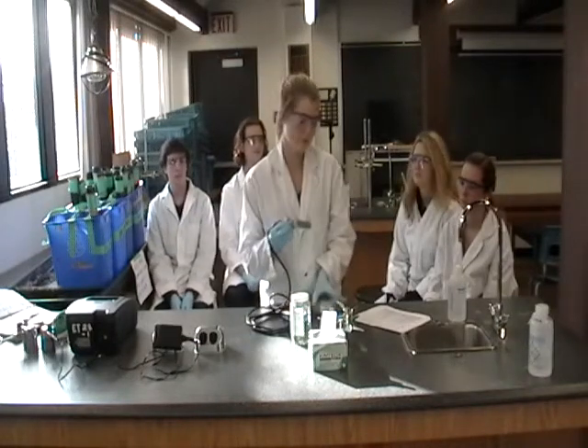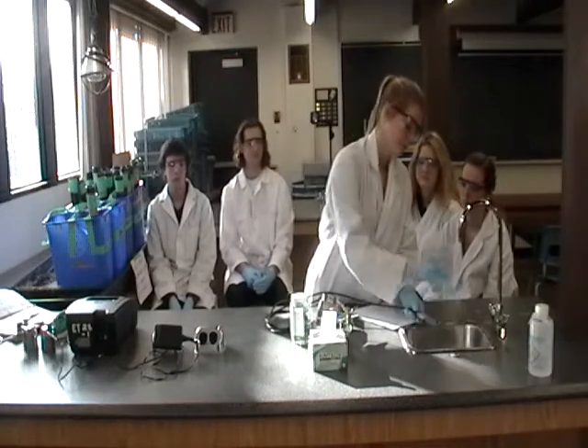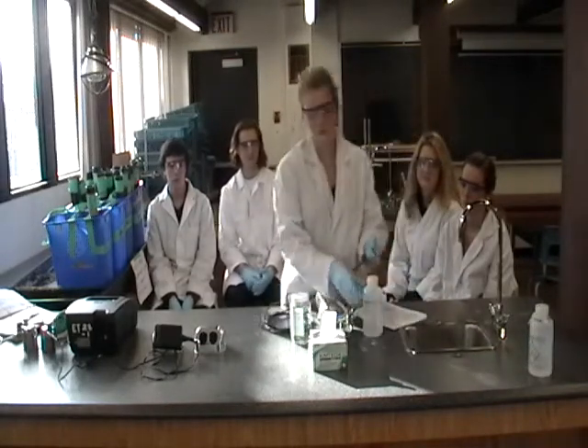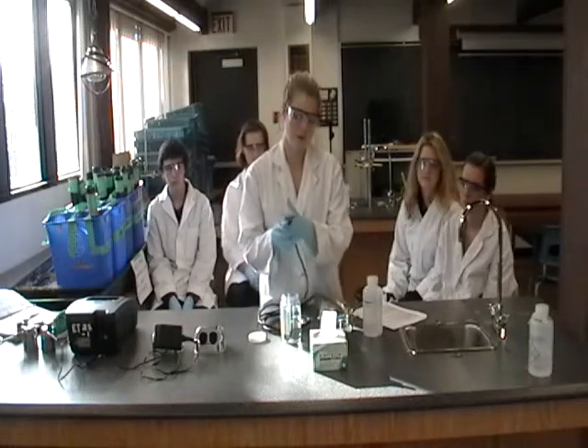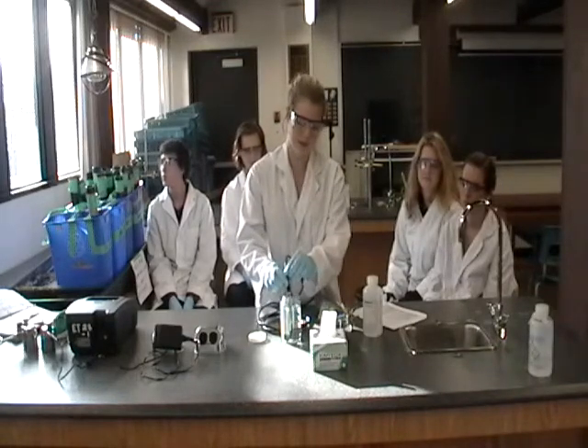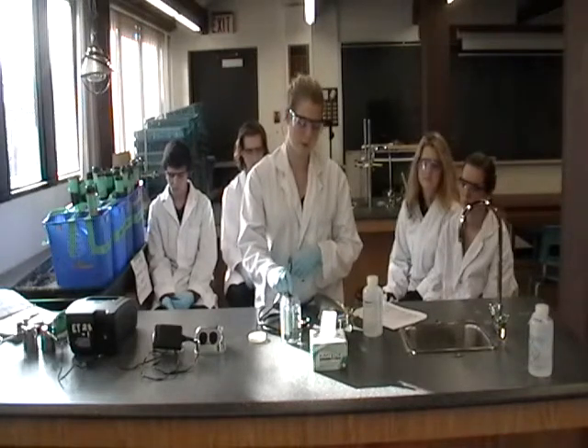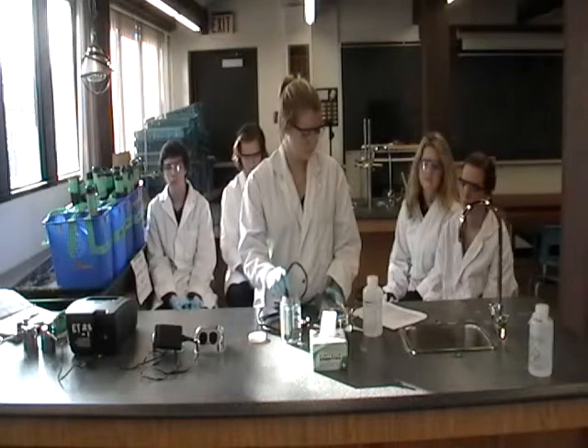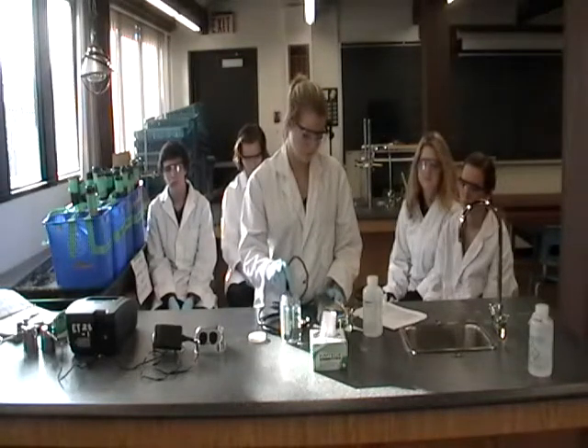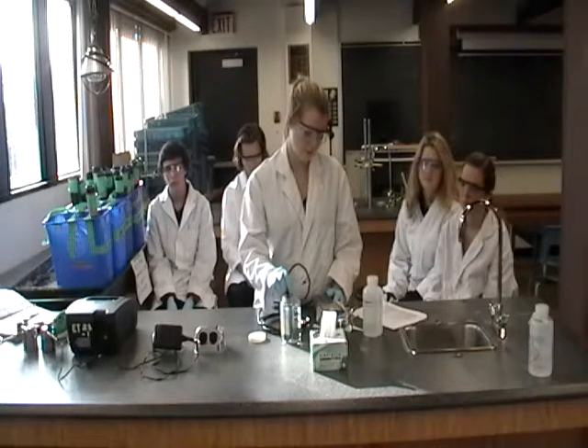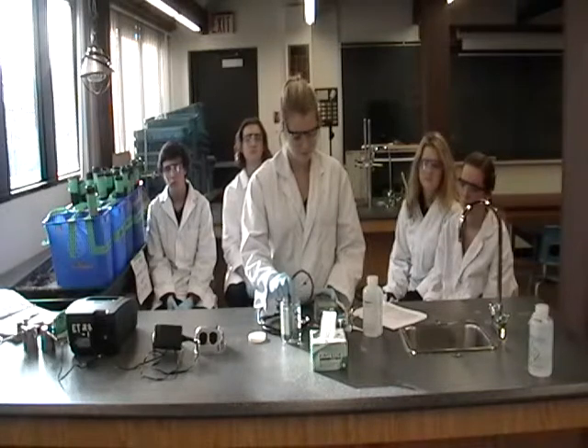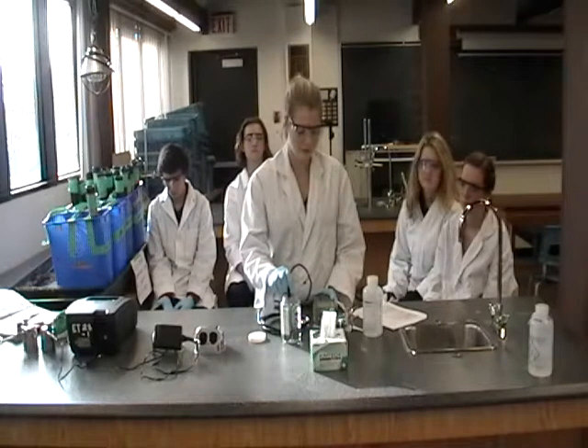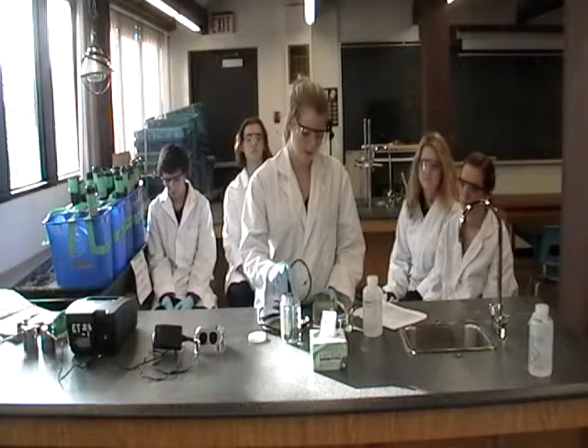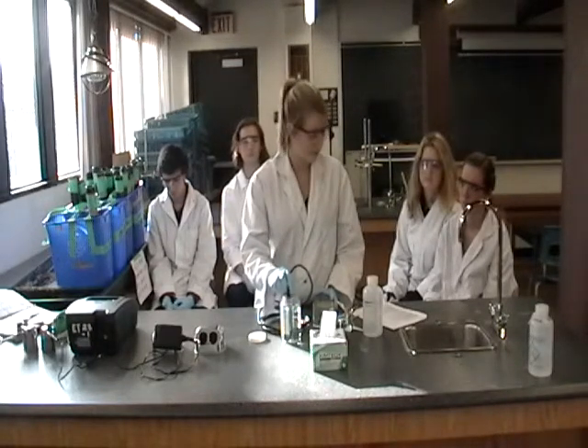You want to take your probe out, you want to rinse it with distilled water. And then this is our sample water from the tap. You want to insert the probe into the water, and while you're taking the reading, you want to continuously bob the probe up and down. And you want to wait for it to become stable. Alright, and the reading is going to be 432.0 microsiemens. And the temperature of the water right now is 19.5 degrees Celsius.